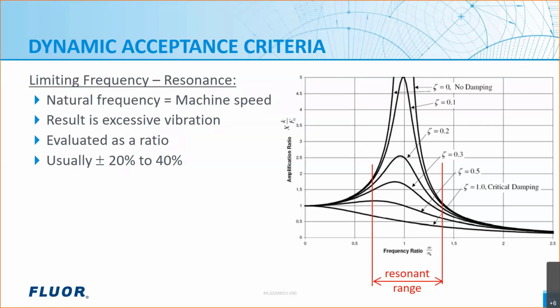The chart shows the frequency ratio on the horizontal axis versus amplitude on the vertical axis for several dark line values of damping. A frequency ratio of 1, when the natural frequency equals the machine speed, plus a low damping ratio results in the sharp peak shown in the middle. The design intent is to avoid resonant frequencies within the specified resonant range, as indicated in red. Depending on the applicable specification, the specified resonant range is generally plus or minus 20 to 40% of the machine speed. Complicating factors include variable speed operation. However, the amplitude of response is the primary concern.